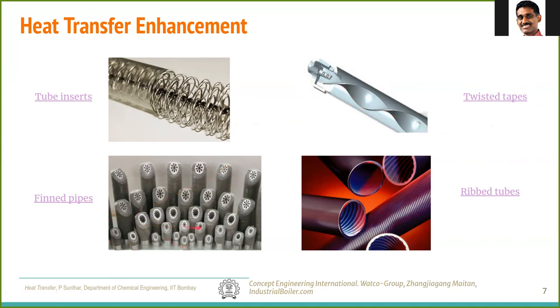The third case is finned pipes, where fins protrude inside the pipe — similar to the conduction fins discussed earlier — increasing the internal surface area and thus heat transfer. However, both tube inserts and internal fins cause a severe pressure drop. A third variant called rib tubes has ribs along the inside; they don't block the flow as much and offer a compromise between pressure drop and heat transfer improvement.